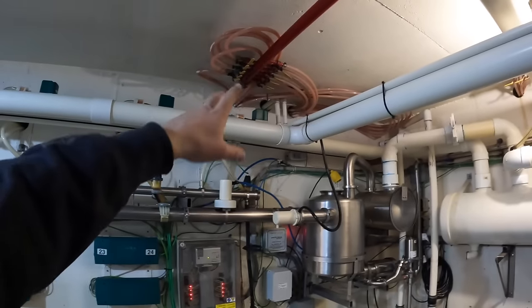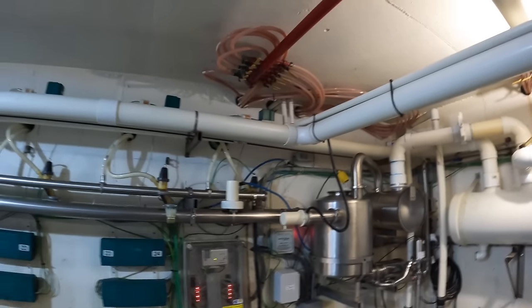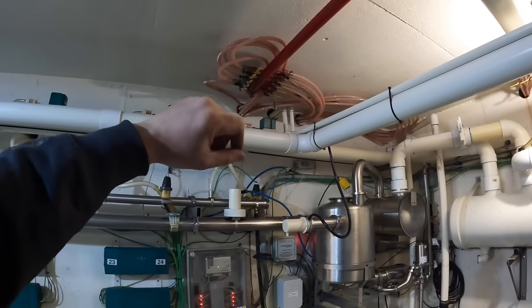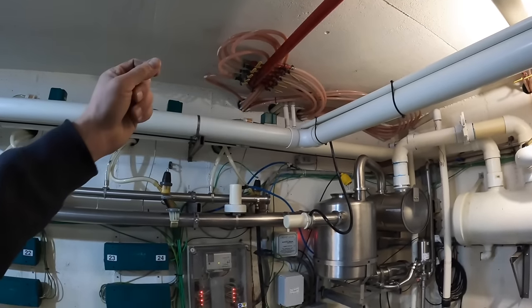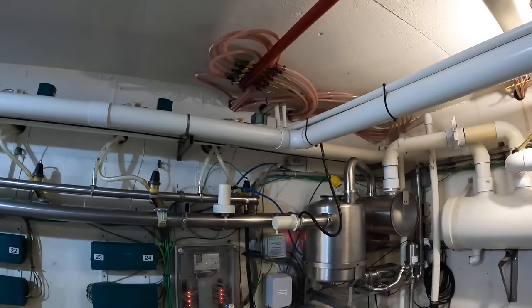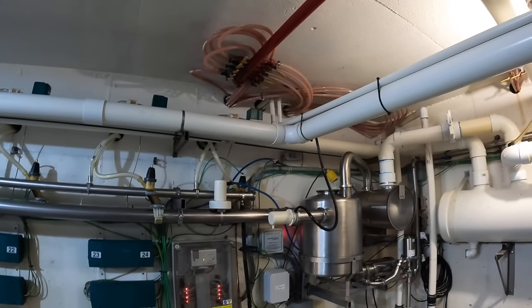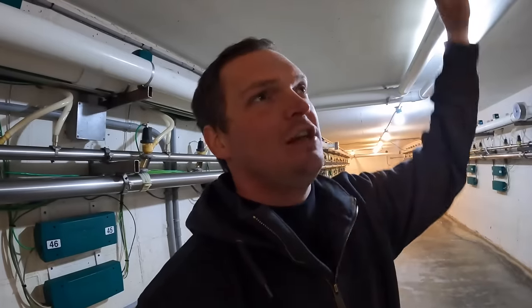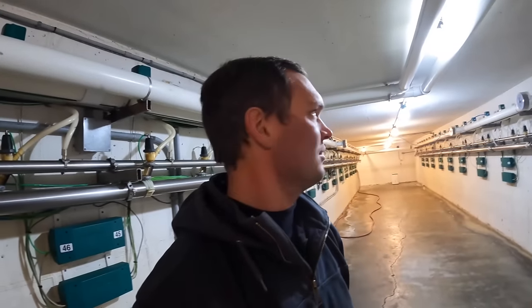So I opened these up, turned the thermostat up to get them to run, and this is an in-floor thermostat, so it's measuring the floor temperature. That was at 55 degrees, and since I turned that up, opened these back up, turned the pumps on, I got it up to 90 degrees now. And we haven't lost pressure on the boiler, and I can feel just by touching the ceiling here that it's warmer than it was before.